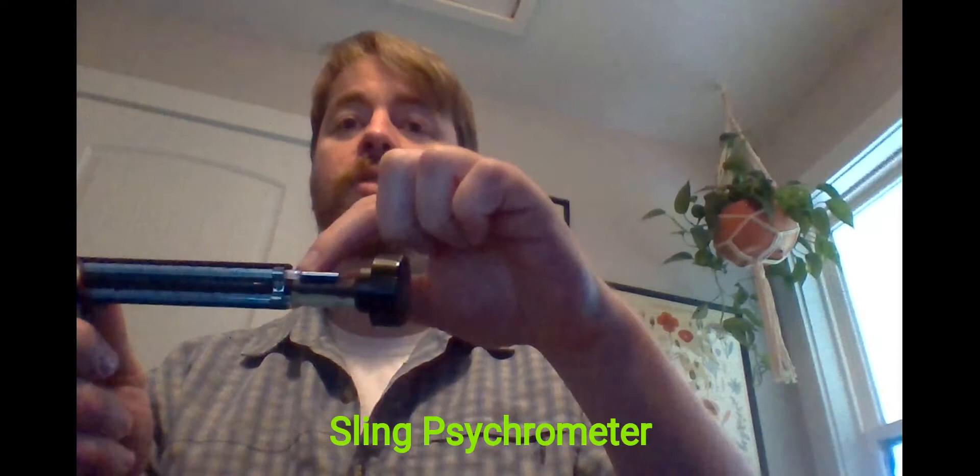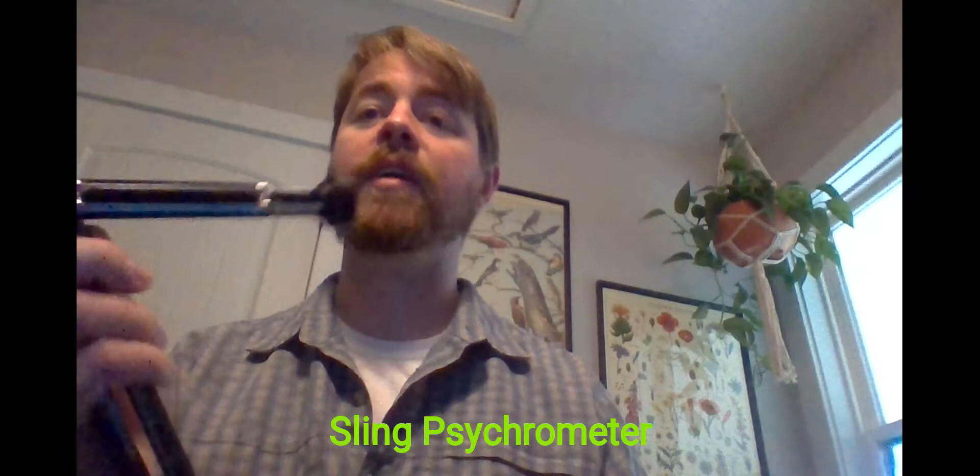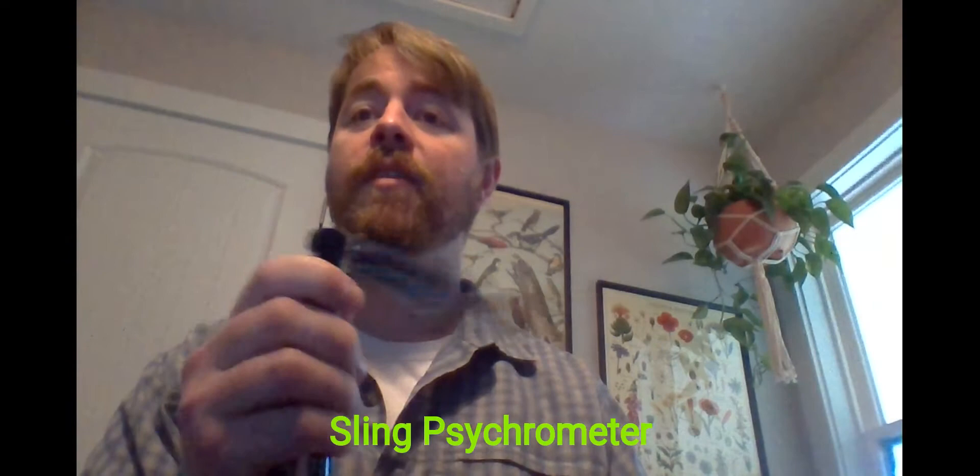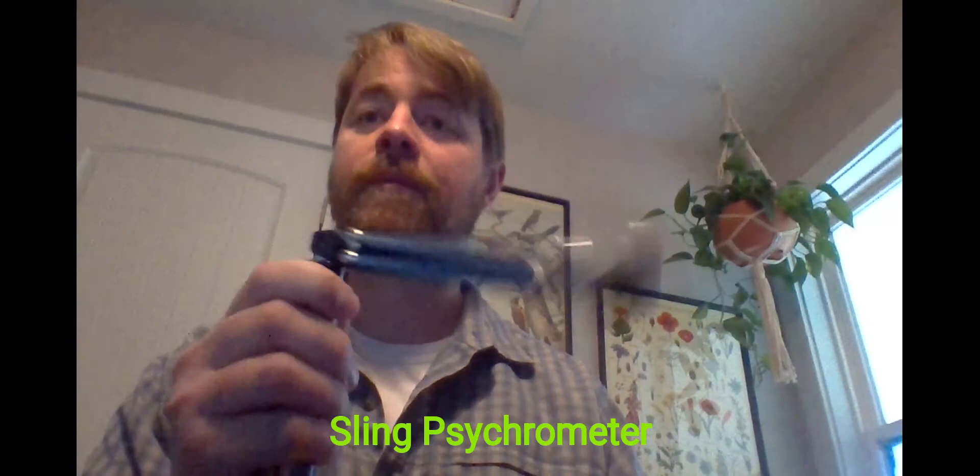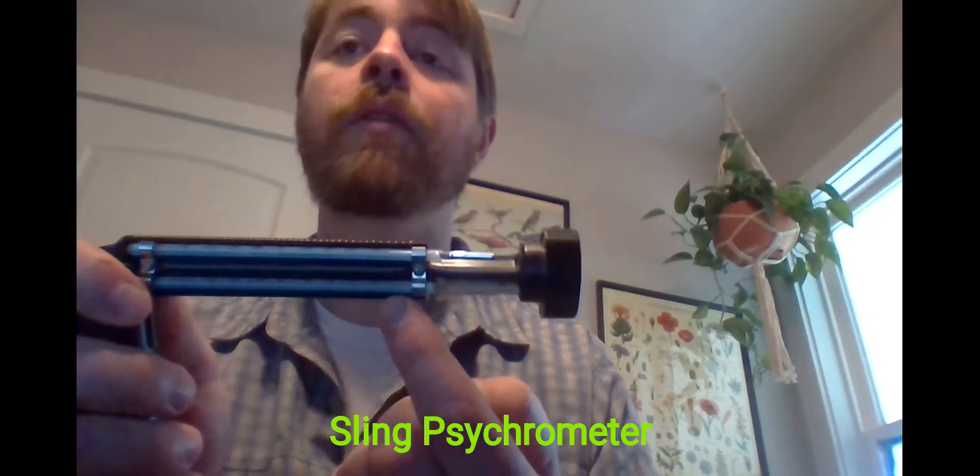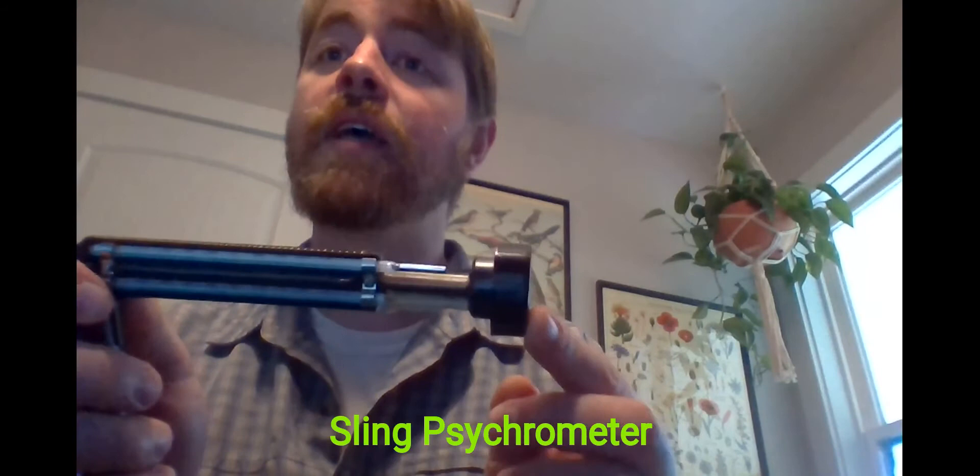The top bulb, we call it the dry bulb, gets the actual air temperature. And then as we spin the sling psychrometer, the wet bulb, the water evaporates and it takes away heat, which changes the temperature in the thermometer. The more it changes, the more water evaporated, which means there's a low humidity. Once we've spun it for a minute or two, we can look at the thermometers and see how big the difference in the temperatures is. The greater the difference, the lower the relative humidity. If the temperatures are really close together, that means the air already has a lot of moisture in it and not much evaporated.